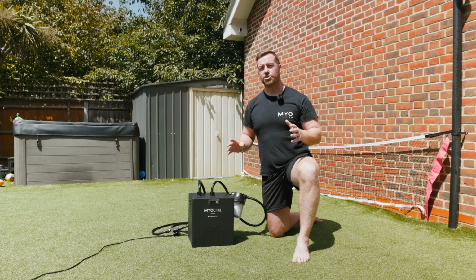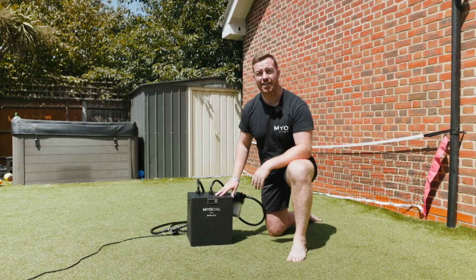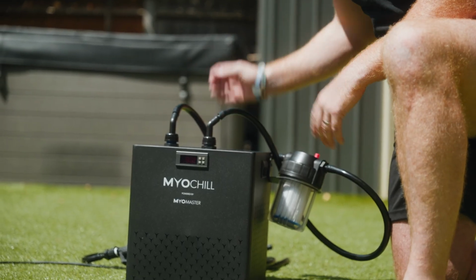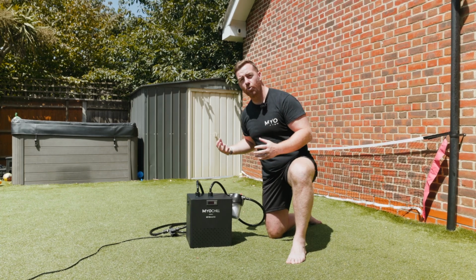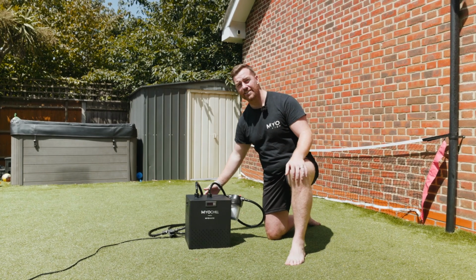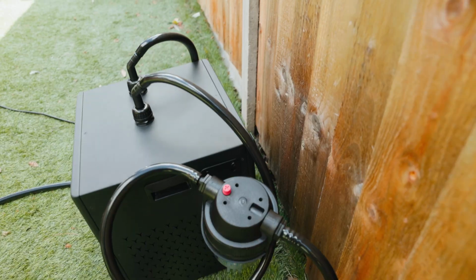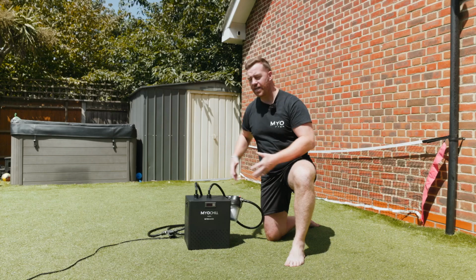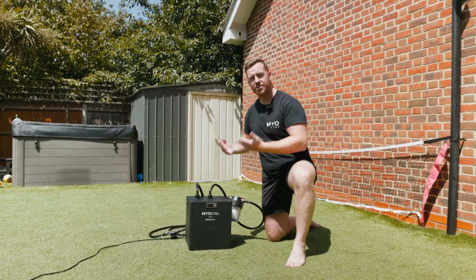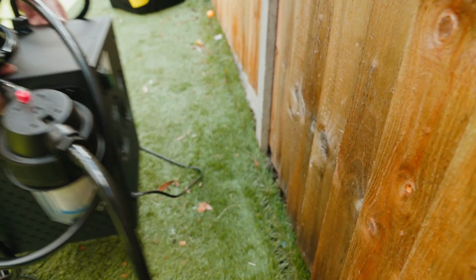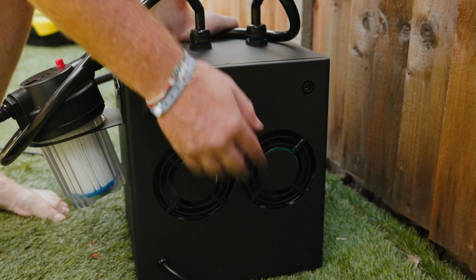So the second thing I want you to try is to make sure that your chiller has sufficient airflow around the chiller. So what it does is it draws the heat from the water and disperses it out of the fans at the back. So if the fans are blocked or too close to a wall or fence, the heat will stay around the chiller and build up all the temperature within. You want it around 60 centimeters away to give good airflow behind the chiller.